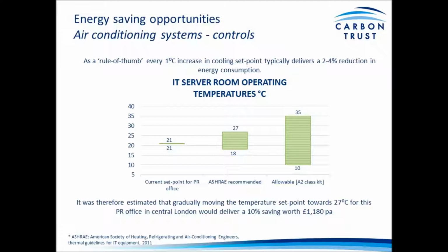Just to reiterate the point for IT server rooms, the guidance temperatures that are given here are from ASHRAE, the American Society for Heating, Refrigeration and Air Conditioning Engineers. And as you can see, in this particular example, this PR company was operating the server room at 21 degrees C, but incrementally changing the temperature towards 27 degrees C reached a 10% saving worth over £1,000 per annum. So it's worth having that discussion with your IT teams to try and increase the temperature of your server rooms. And as a rule of thumb, every 1 degree C increase in cooling temperature set point typically delivers a 2 to 4% reduction in energy consumption. So worthwhile discussing, and it's worth the battle with IT teams to get that changed if you can, because it's quite an easy energy saving.